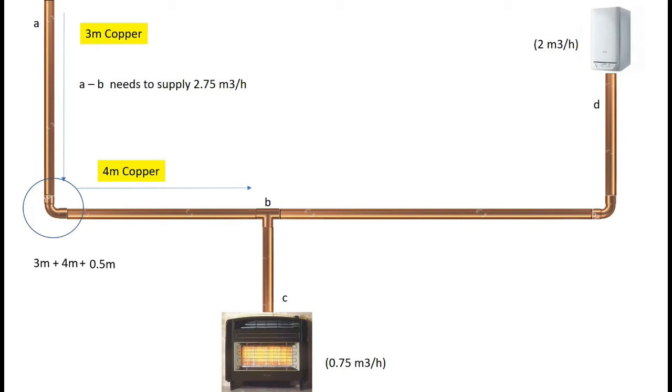Every bend, my apologies, for the elbow. Every elbow and every T piece, you add 0.5 of a meter to your calculation. In this, between A and B, we're not counting the T piece at B. That will be counted later on when we pipe size between B and D. You only use a fitting once in your calculations.